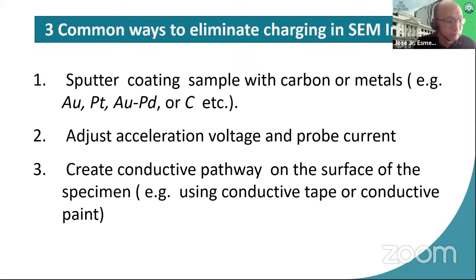So this is how the sputtering happens. This is a magnetron-type sputter coater, which was shown before by Dr. Camacho. We have the platinum target here, which creates a plasma. This plasma creates sputtering that coats the sample. What happens is that you have a non-conducting sample, and this conducting element is coated on your sample, so you have some sort of conductive path to ground.